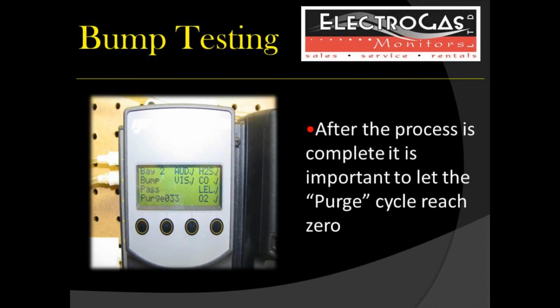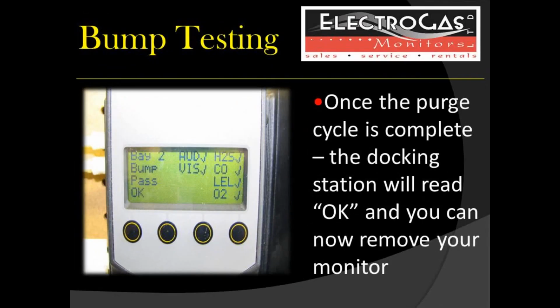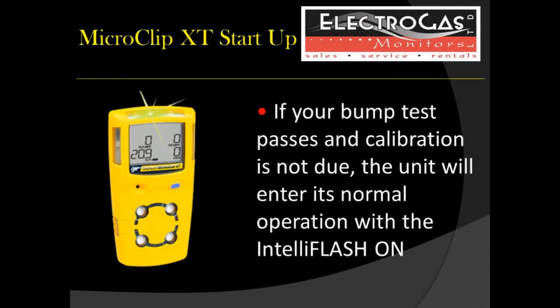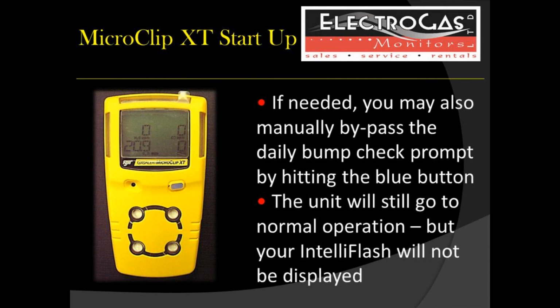After the process is complete, it is very important to allow purge clock to set to 0. Once the purge cycle is complete, the docking station will read OK, and it is now safe to remove your monitor. If your monitor has passed all its function tests, as well as the bump test, and calibration is not due, the IntelliFlash or green light will come on as your monitor enters normal operation mode. If needed, you may also manually bypass the daily bump check prompt by hitting the blue button. Your unit will still go into normal operation mode, but your IntelliFlash will not be displayed.